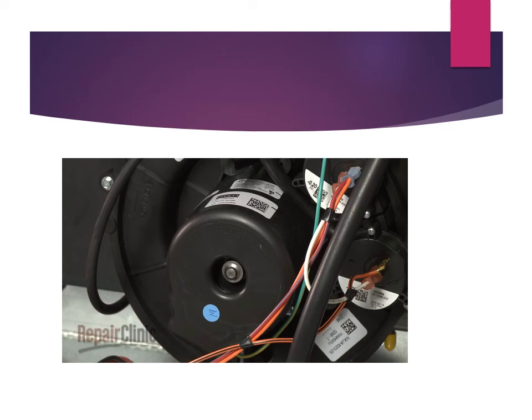The inducer fan is one of the most common problems — it goes bad a lot in gas furnaces because it undergoes a lot of pressure, and also because filters don't get changed. The filter draws air through the heat exchanger; if you don't change it every one to two months it gets clogged, the inducer fan overworks, and eventually the motor burns out. From the troubleshooting video you'll see if it's overheated or cracked — that means it's overworking and probably time to replace it.